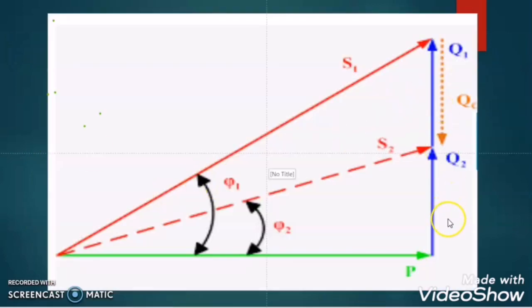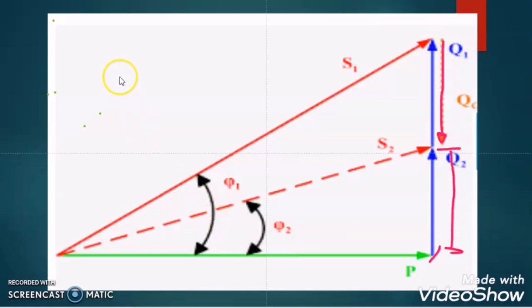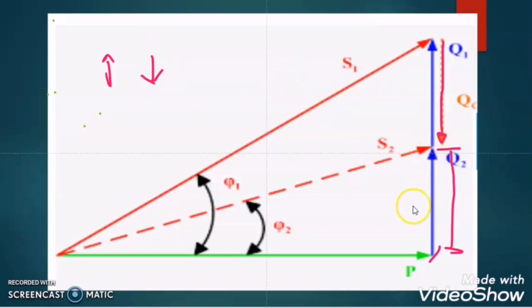From this triangle you can understand it better. Suppose this is the active power and this is the reactive power when there is no capacitor — all are inductive loads. If we add one capacitor bank, then it will compensate this amount of reactive power from the system and the final reactive power will be reduced. If the reactive power is more, then the power factor will be poor. As we connect the capacitor bank, the reactive power becomes low, so the power factor automatically becomes higher, near to unity.